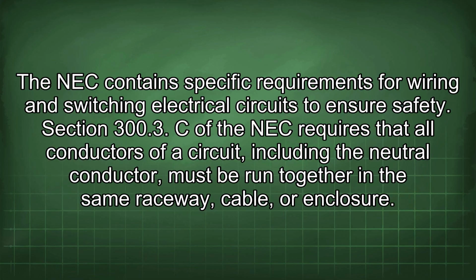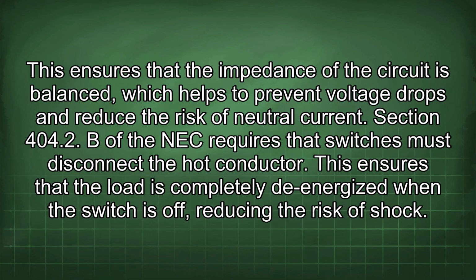The NEC contains specific requirements for wiring and switching electrical circuits to ensure safety. Section 300.3(C) of the NEC requires that all conductors of a circuit, including the neutral conductor, must be run together in the same raceway, cable, or enclosure. This ensures that the impedance of the circuit is balanced, which helps to prevent voltage drops and reduce the risk of neutral current. Section 404.2(B) of the NEC requires that switches must disconnect the hot conductor.